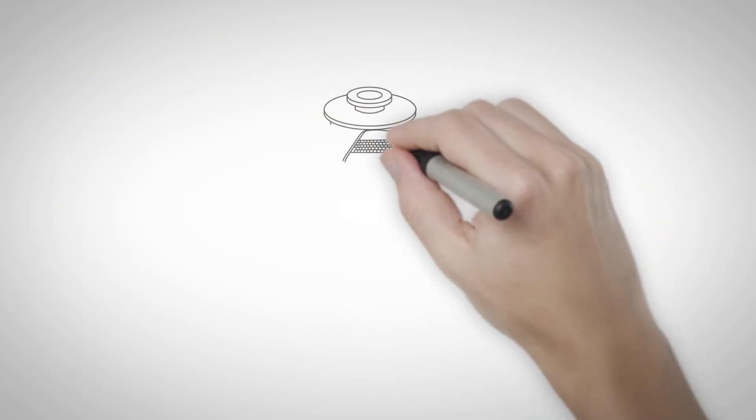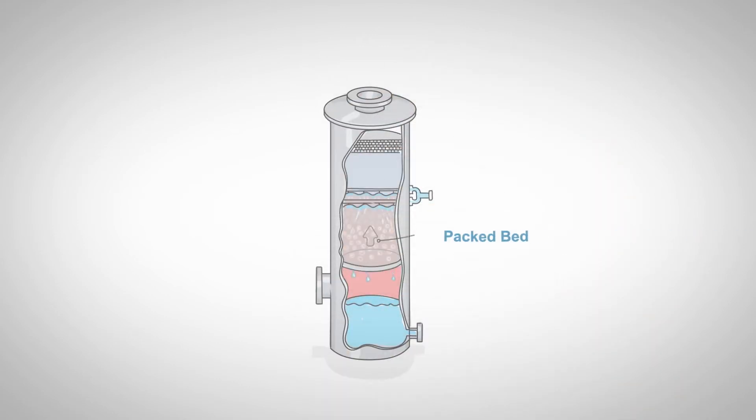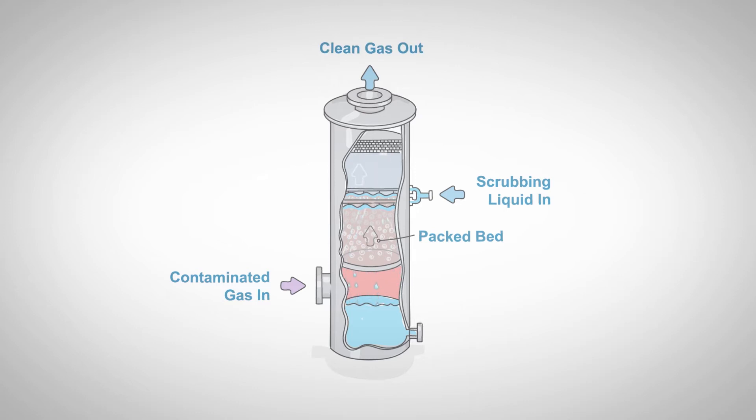With packed bed scrubbers, packing material is layered to create a large surface area for liquid particle contact. Contaminated gas enters at the bottom, and it meets a scrubbing liquid that is sprayed down from above the packing. Contaminants are then absorbed into the liquid, and the gas stream flows up the chamber through a mist eliminator and exits cleanly at the top.